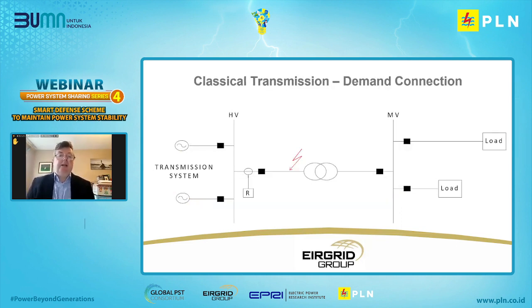So here we're looking at a classical transmission distribution interface. If we get a fault on the HV side of a distribution transformer, all the power flow is from the grid. Can you advance the slide? There's some animation on this, hopefully it works. Okay, can you try and advance the slide? Yeah, super. So if we have a fault on the HV side of a transmission connected distribution transformer, the power flow is from the transmission system to this transformer. Okay, advance please, next slide. And go one more please.